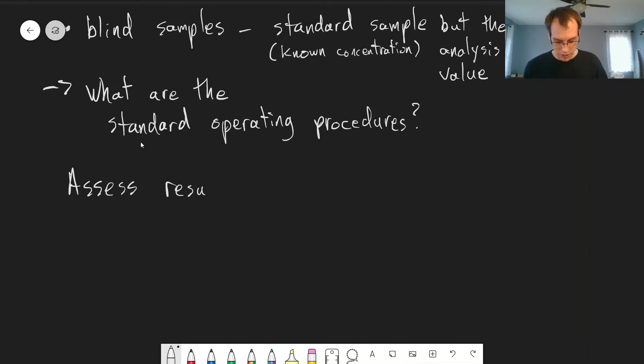So continually be taking spike, doing spike recovery measurements, making sure that over time that stays consistently at 100% spike recovery. Make sure that you're not getting changes in, if you assess results over time, do spike recovery, measure standard samples, and make sure that your results continue to hold up. Even as maybe pieces of equipment age, or different people now are doing the analysis that are running the instruments or running the procedure, that you're still getting accurate results. So this is something that needs to be tracked over time.